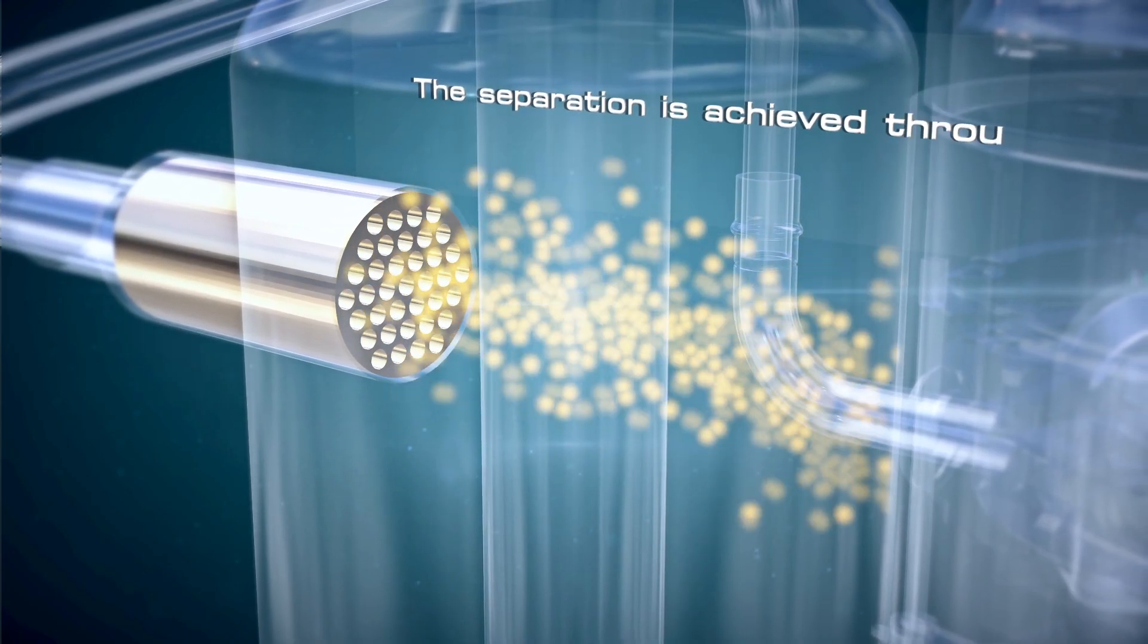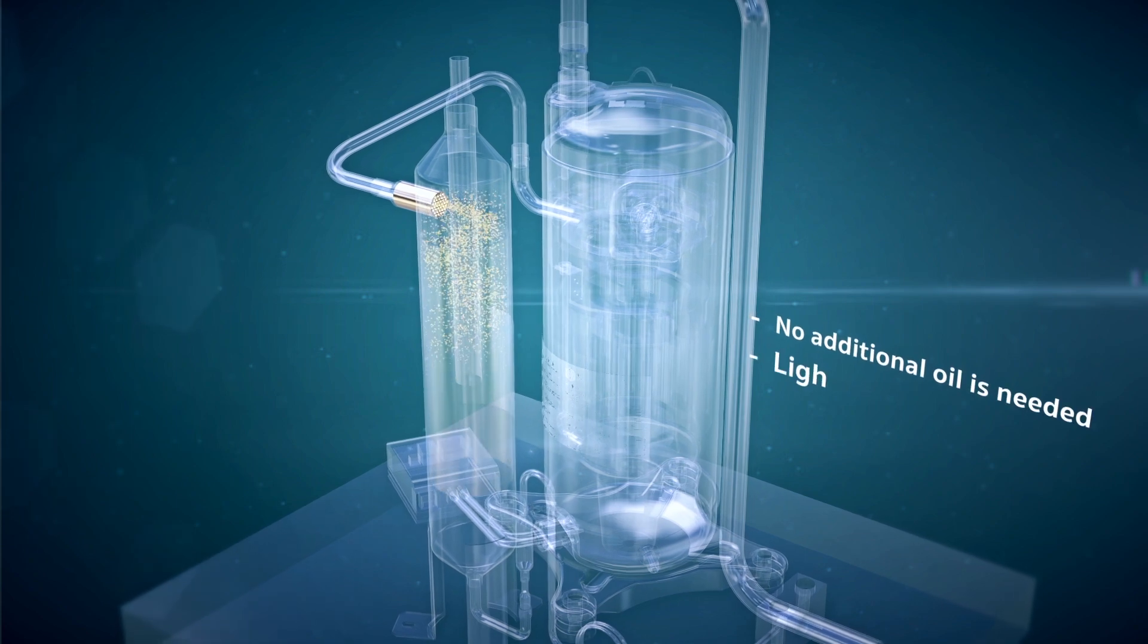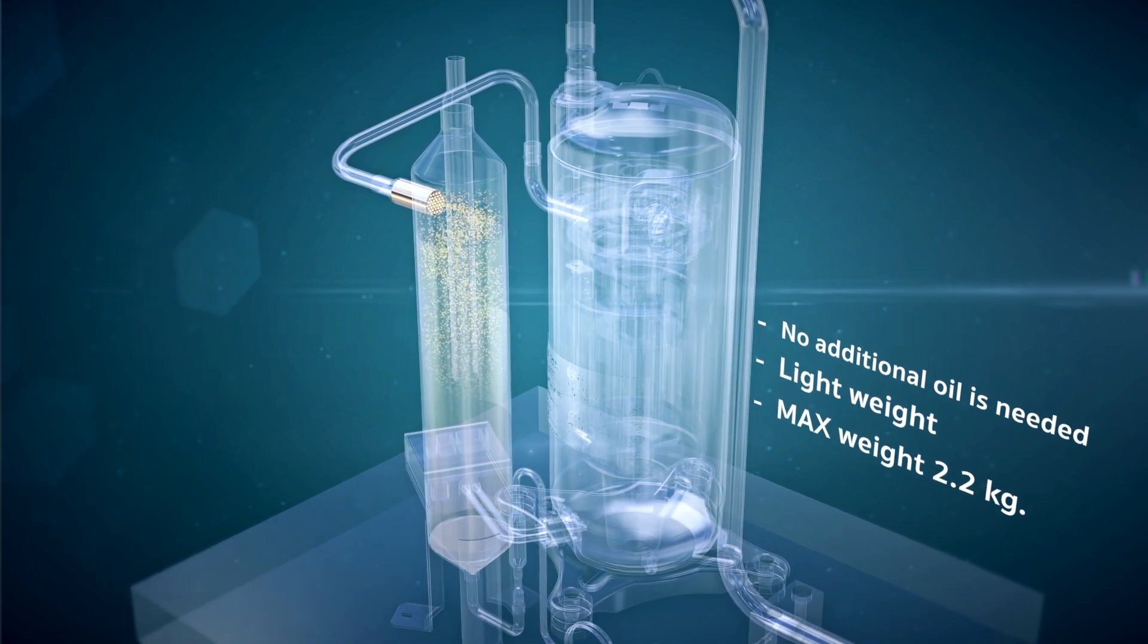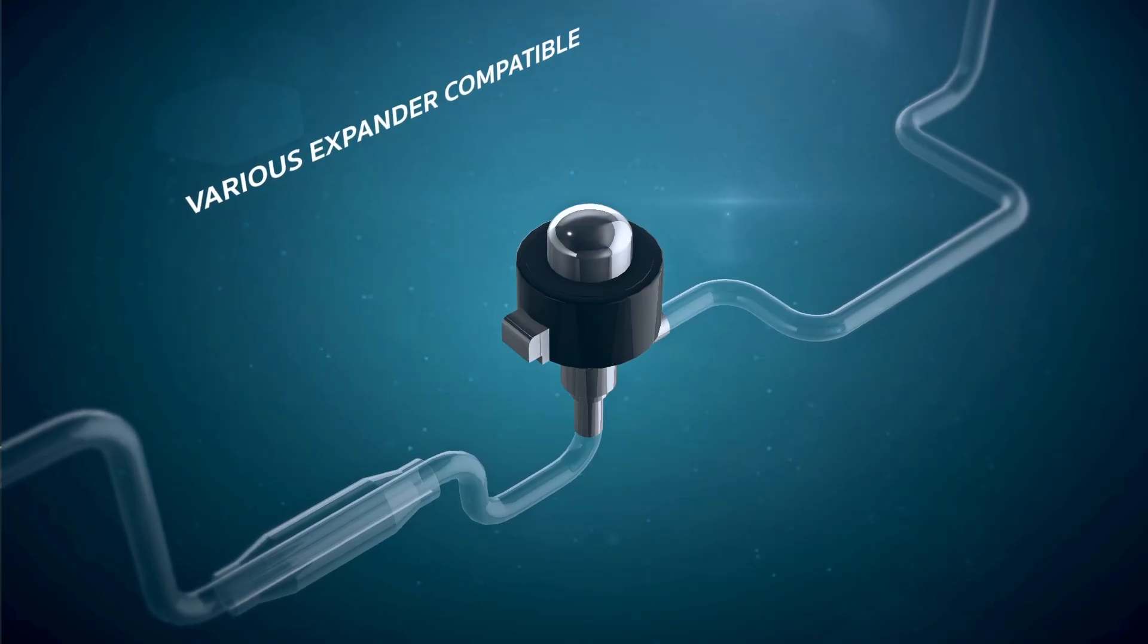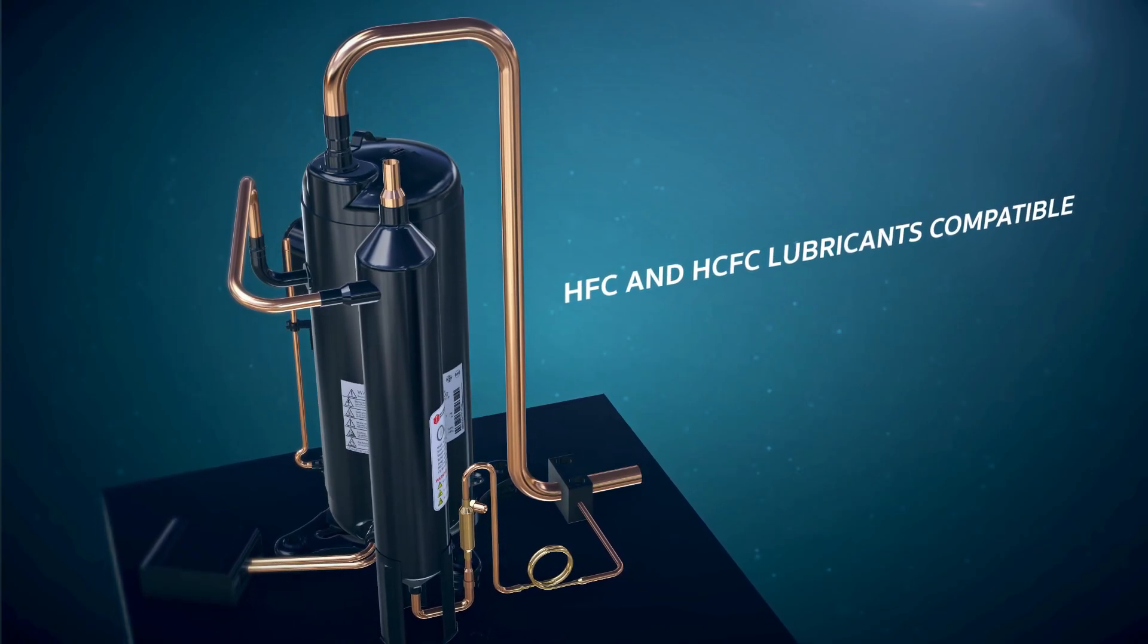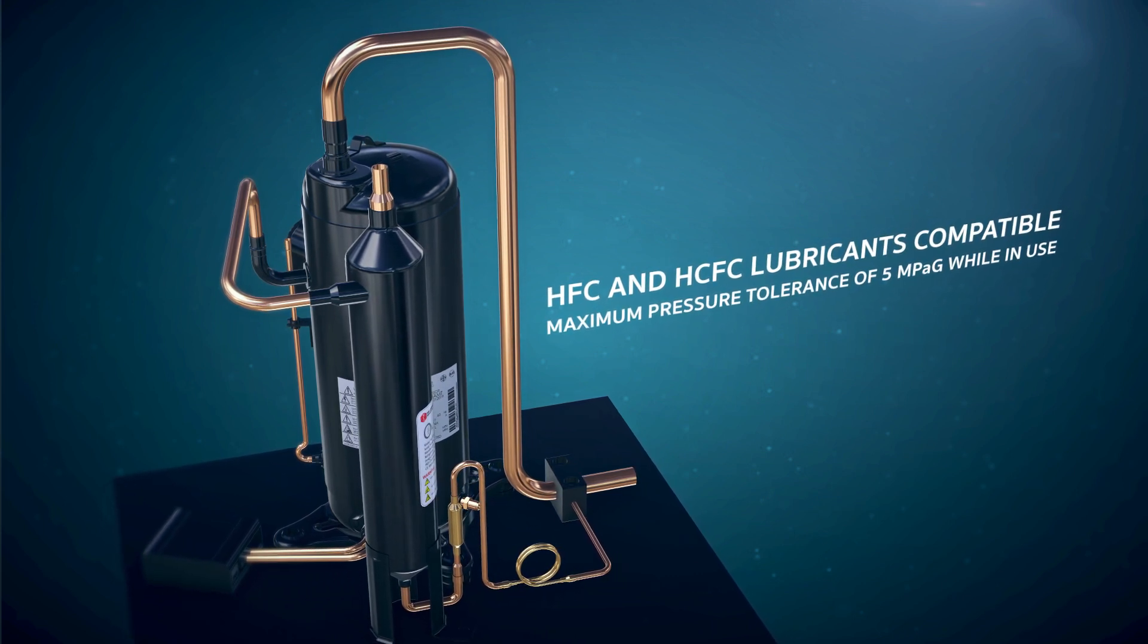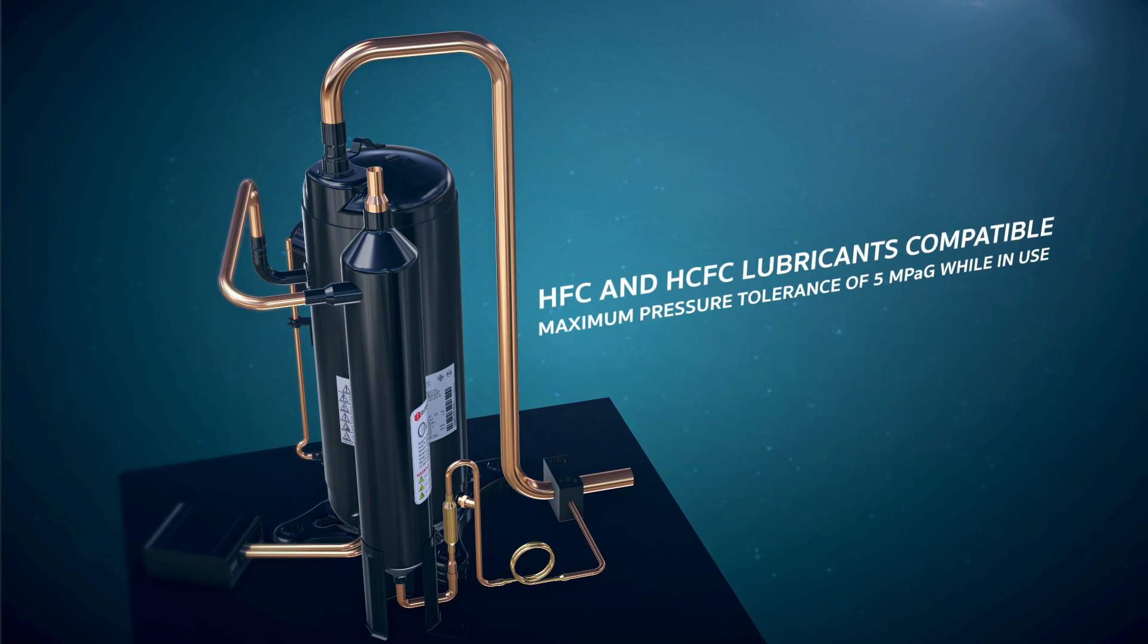The separation is achieved through the use of centrifugal force. No additional oil is needed. It is lightweight, compatible with various expansion devices and HFC and HCFC lubricants, with maximum pressure tolerance of 5 MPa gauge while in use.